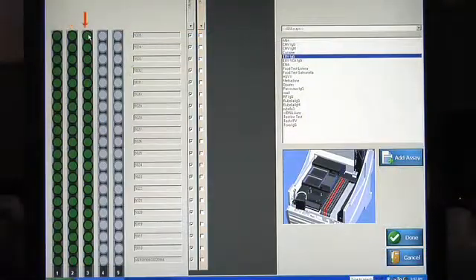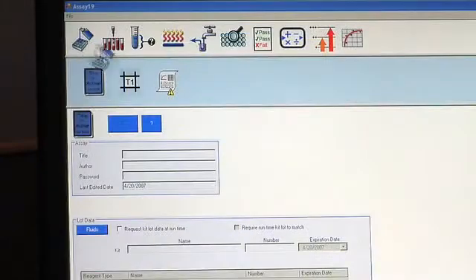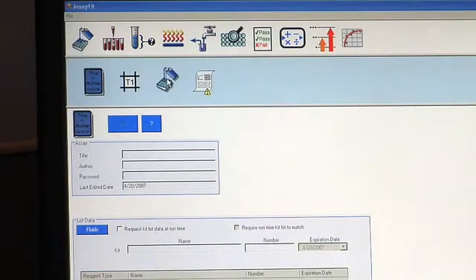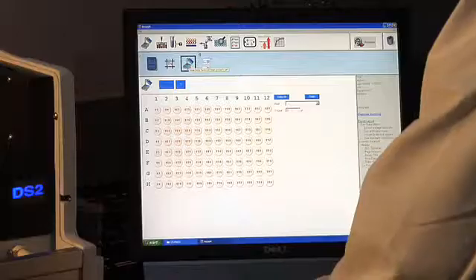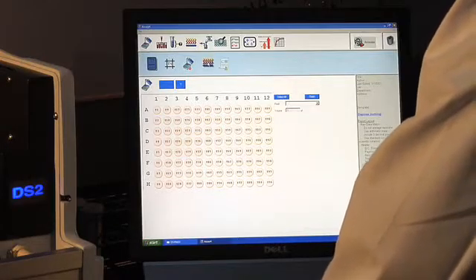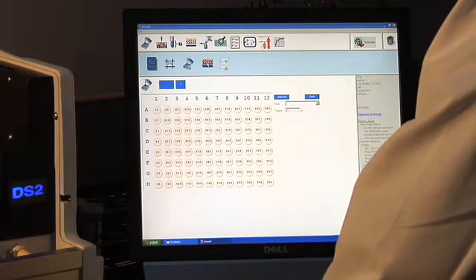DS Matrix will put your requests in queue, schedule, and launch them automatically in the most efficient order. For the systems integrator or lab manager, the Assay Writer makes setting up a new assay to run on the DS2 just as easy.